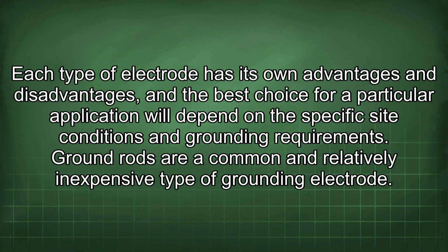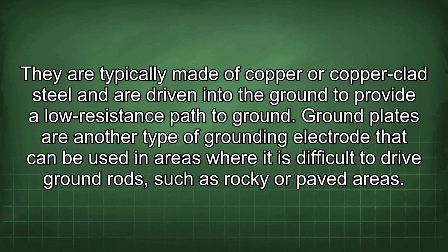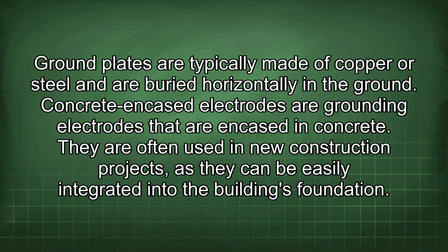Ground rods are a common and relatively inexpensive type of grounding electrode. They are typically made of copper or copper-clad steel and are driven into the ground to provide a low-resistance path to ground. Ground plates are another type of grounding electrode that can be used in areas where it is difficult to drive ground rods, such as rocky or paved areas. Ground plates are typically made of copper or steel and are buried horizontally in the ground.